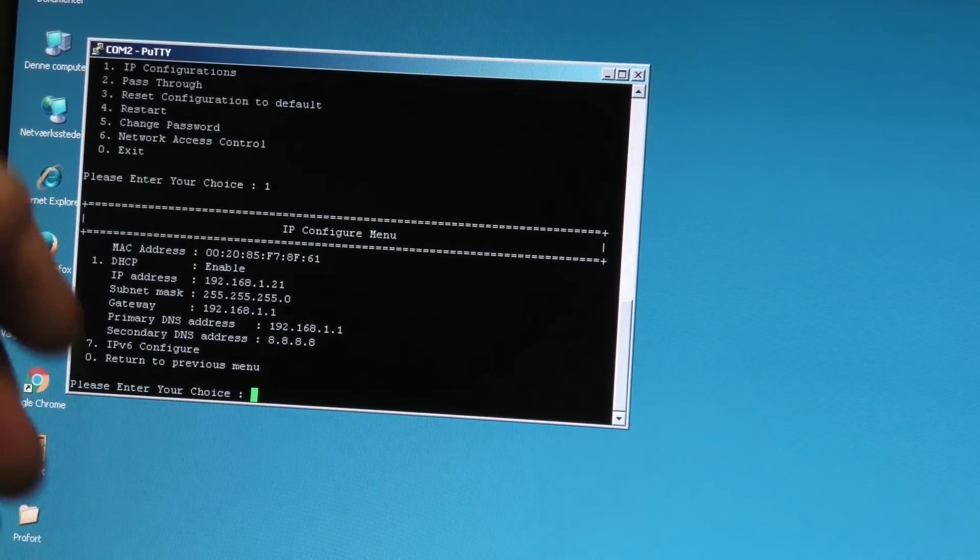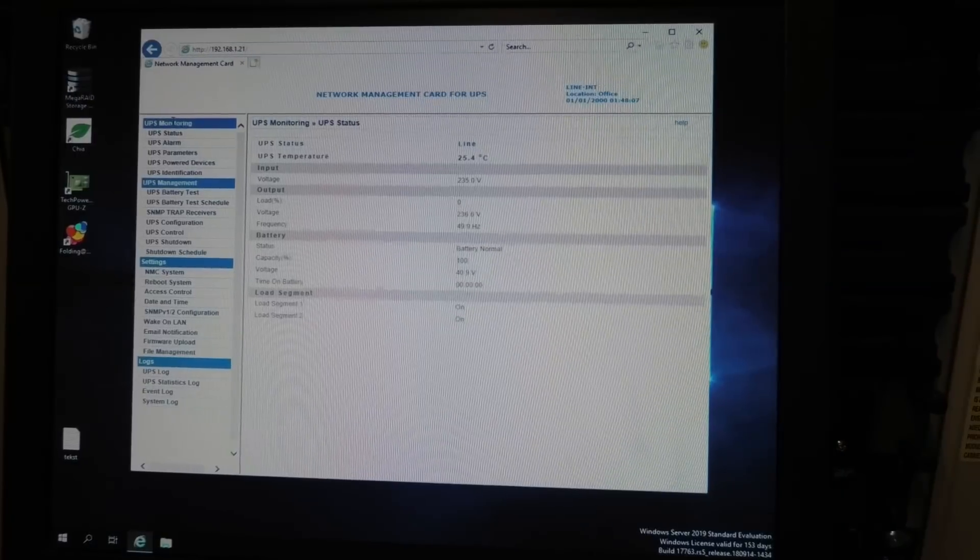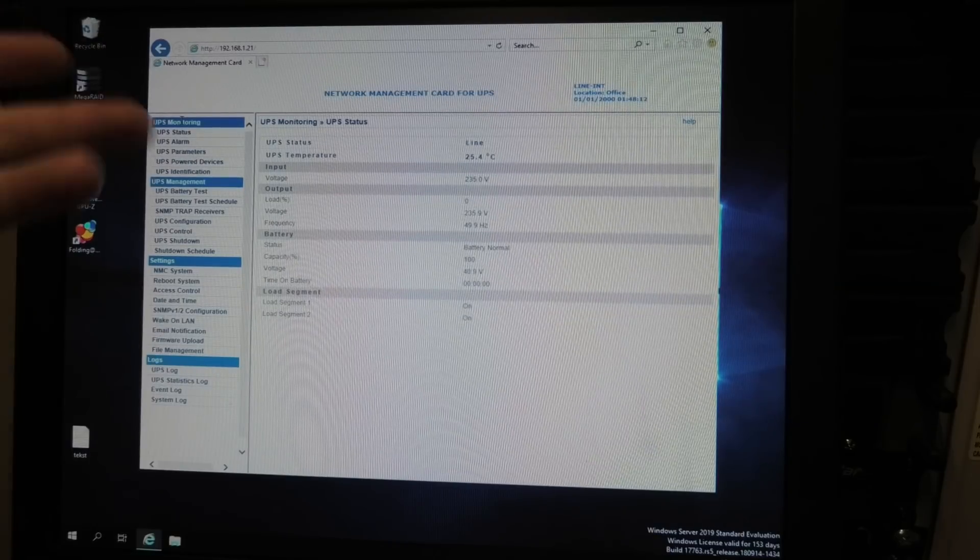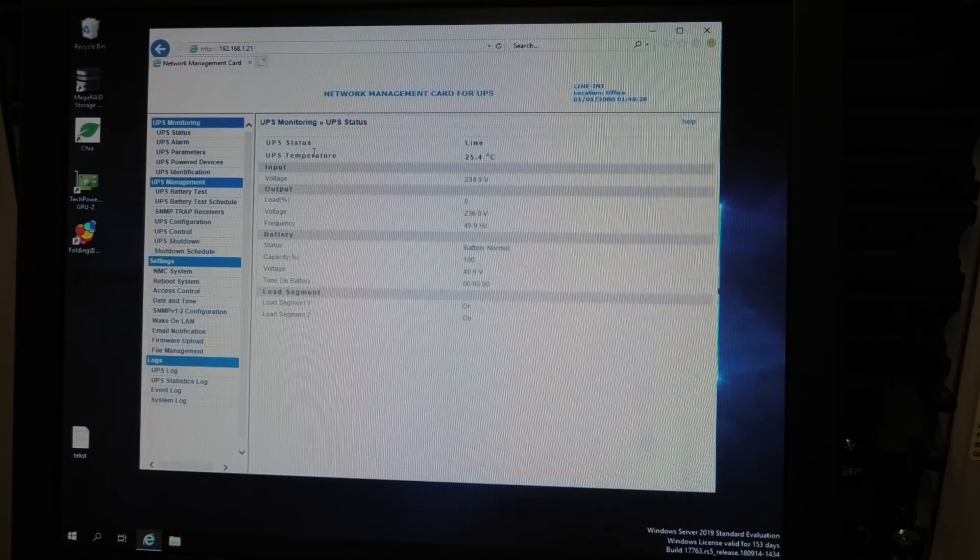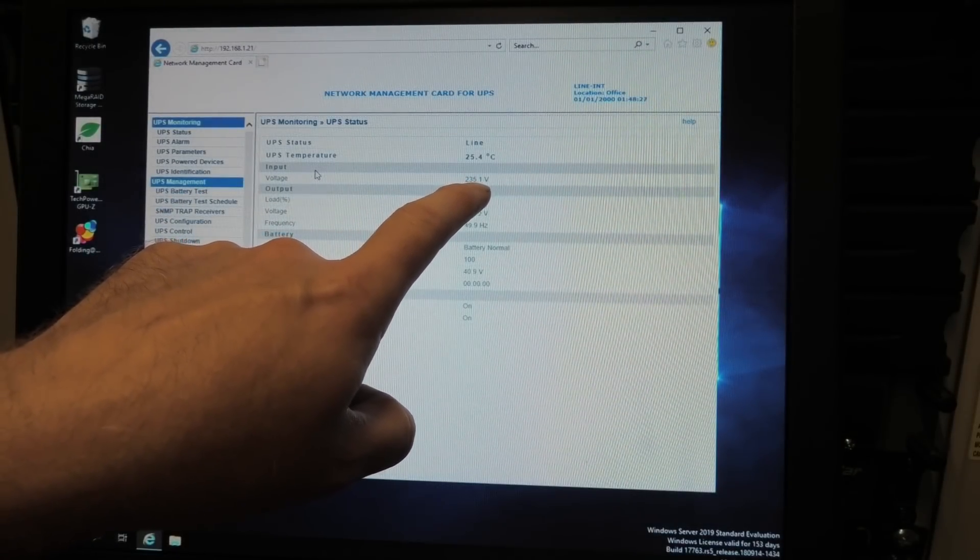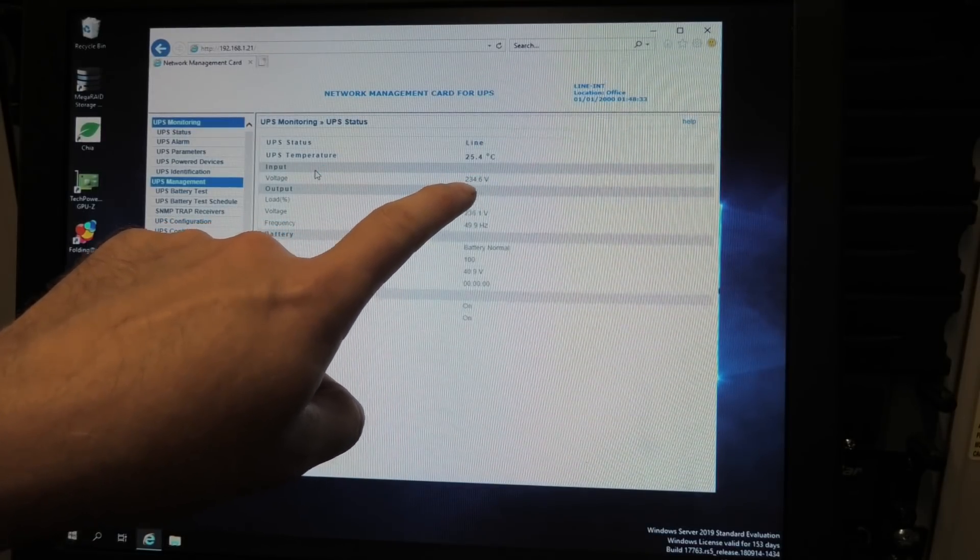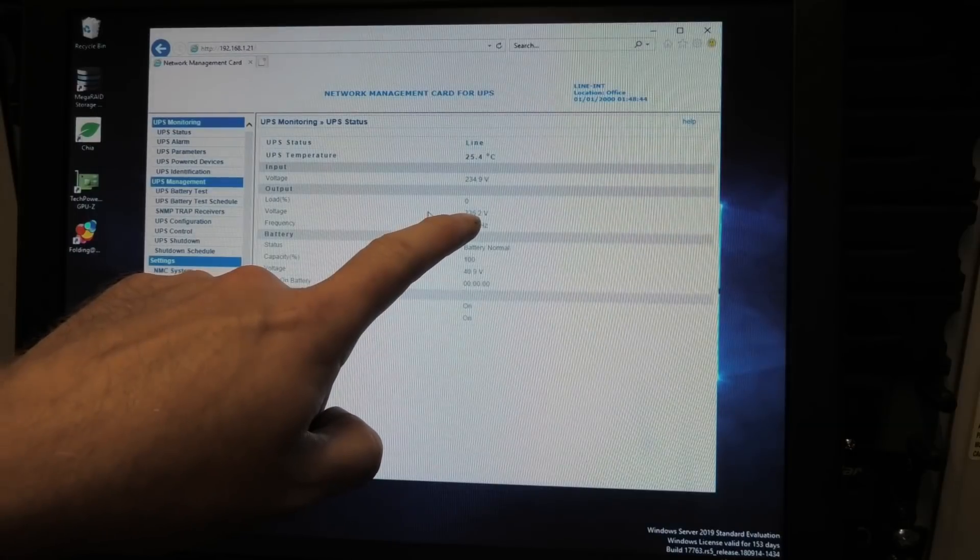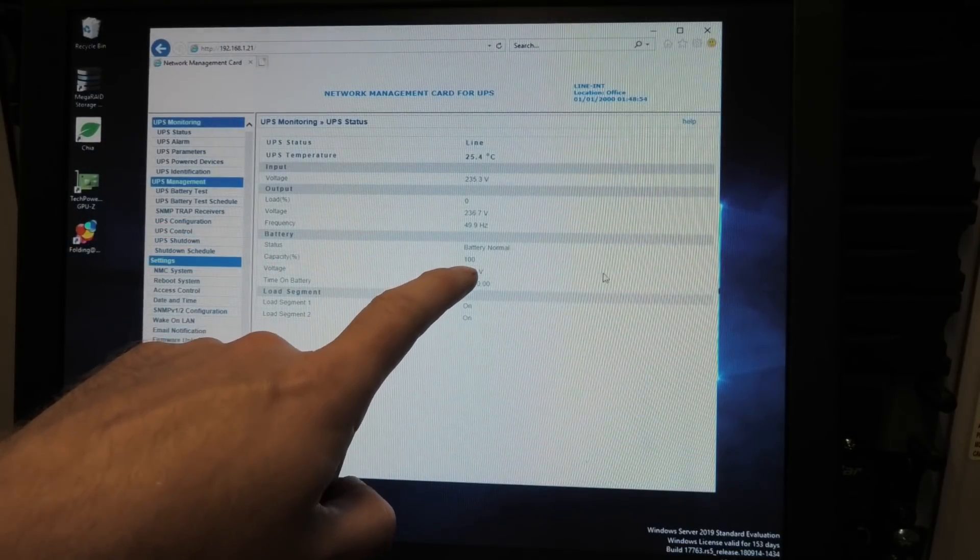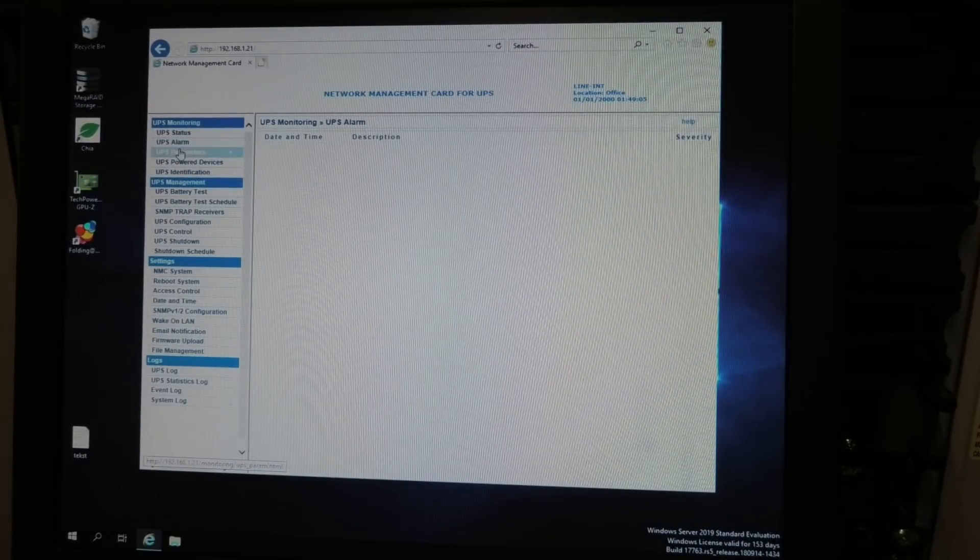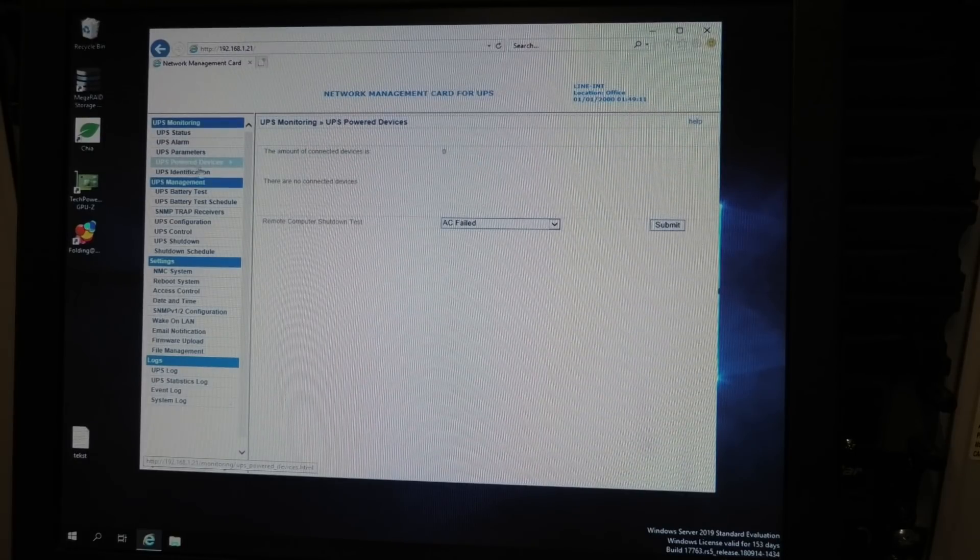That's much easier. I didn't need this old computer. Let's modernize here. Just punch in the IP number in a web browser and you get all the stuff here. It's bloody warm in here, 25.4 degrees UPS temperature. Voltage is at 234, that is ever so slightly higher than I'm used to seeing. It's usually 230 volts. Seems like the voltage has gone up five volts. It's delivering a higher voltage out or there is a difference between measuring in and measuring out. Capacity, batteries 100%.